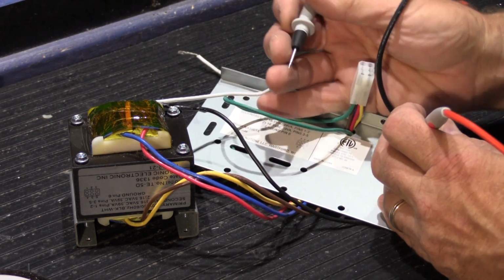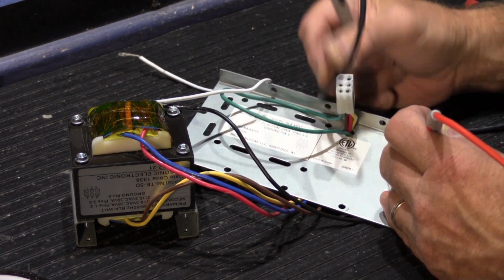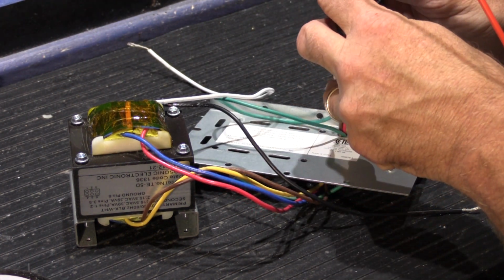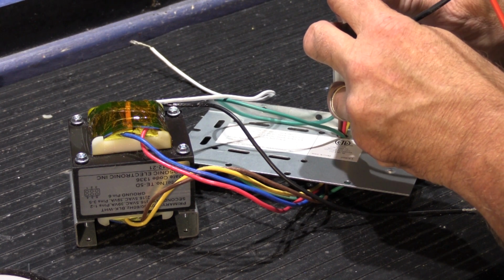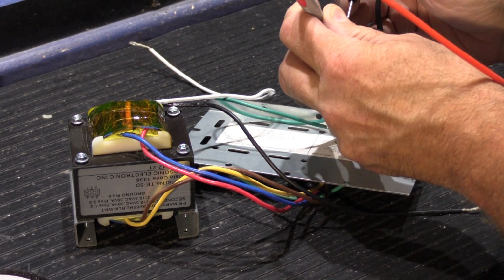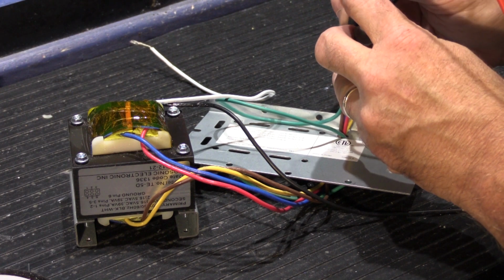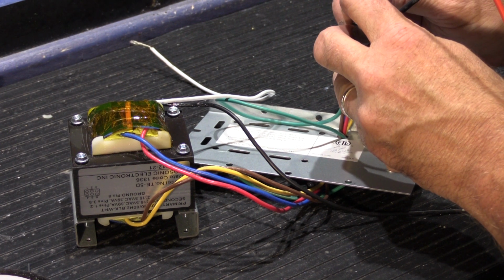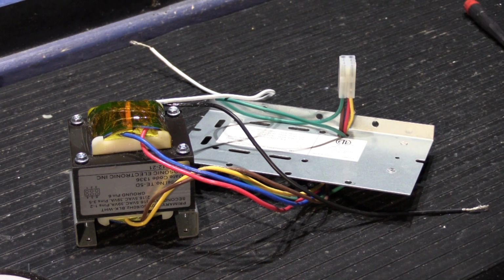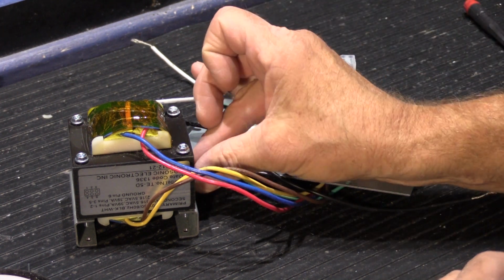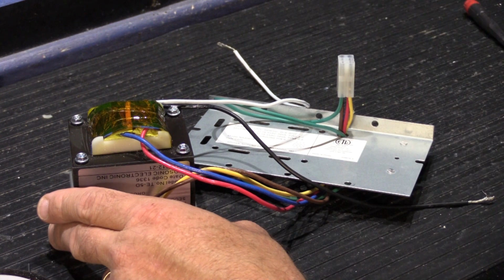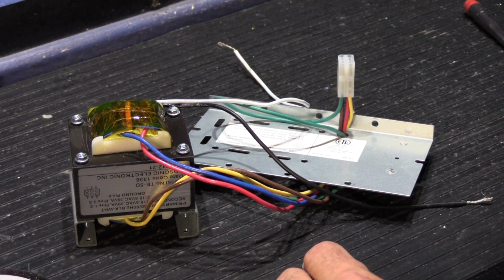So we'll just plug it in and test it here. We'll do blue and red, and it beeps, then brown and yellow, and that's okay too. So we have continuity on both secondary outputs of the transformer, which means there are no fuses on the secondary outputs. The only fuse is on the input.